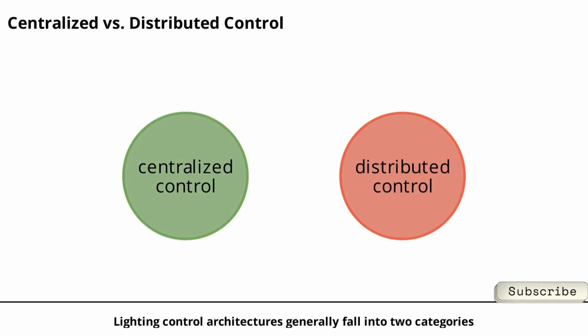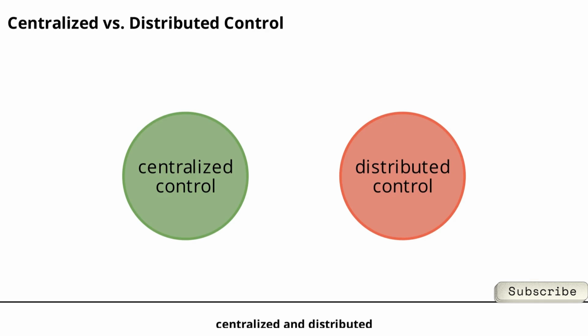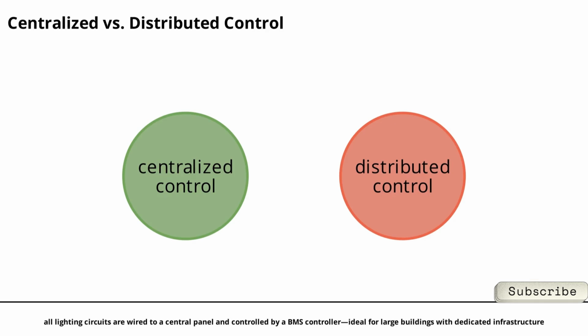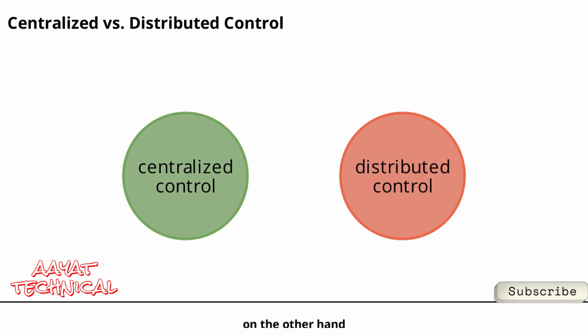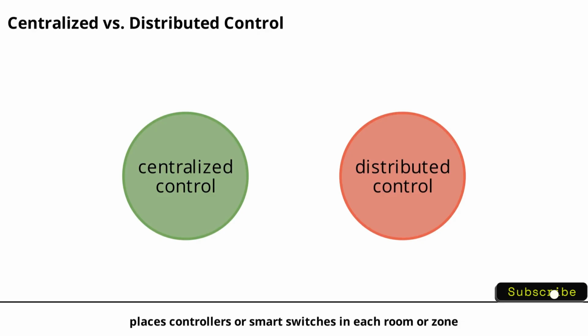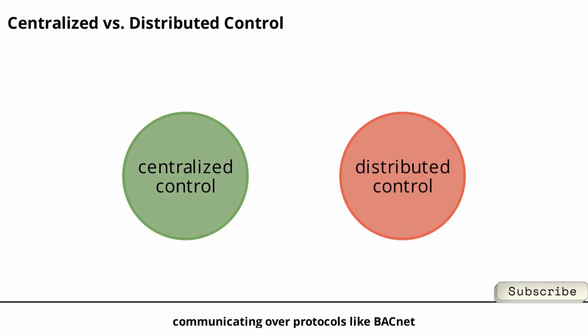Lighting control architectures generally fall into two categories: centralized and distributed. In a centralized system, all lighting circuits are wired to a central panel and controlled by a BMS controller, ideal for large buildings with dedicated infrastructure. Distributed control, on the other hand, places controllers or smart switches in each room or zone, communicating over protocols like BACnet, KNX, or DALI. This approach is often used in retrofits or modular buildings. The choice between these architectures depends on building size, complexity, and future flexibility needs.